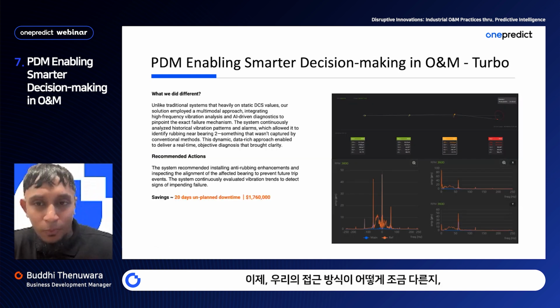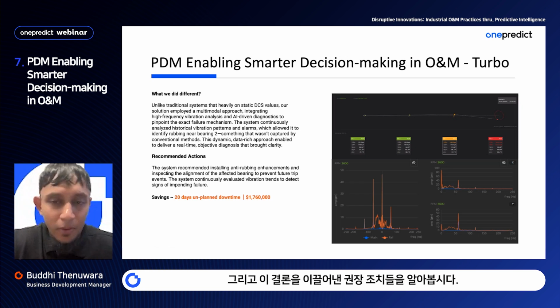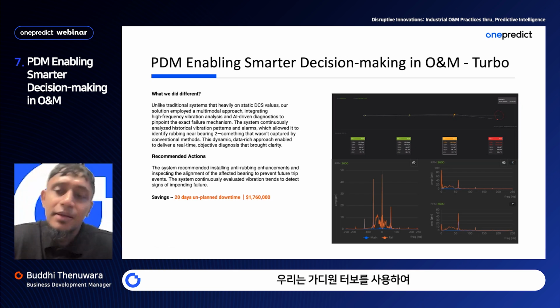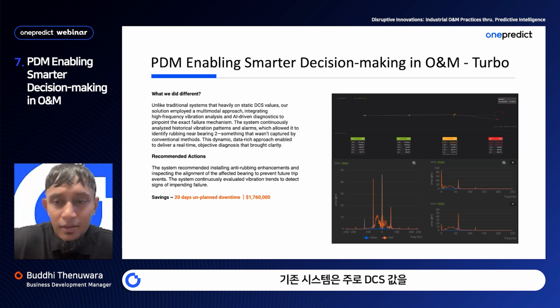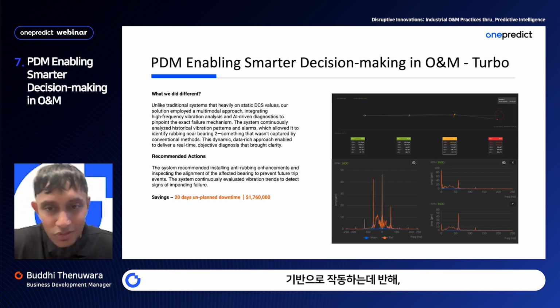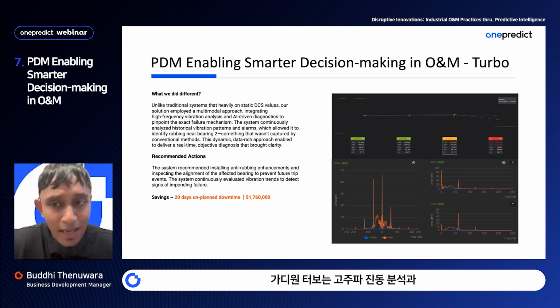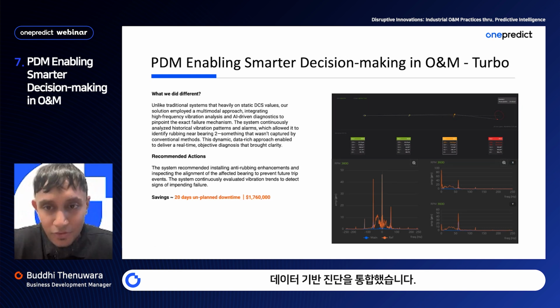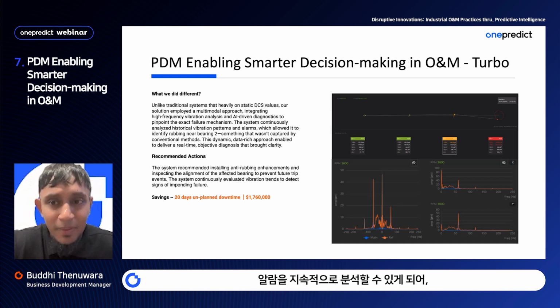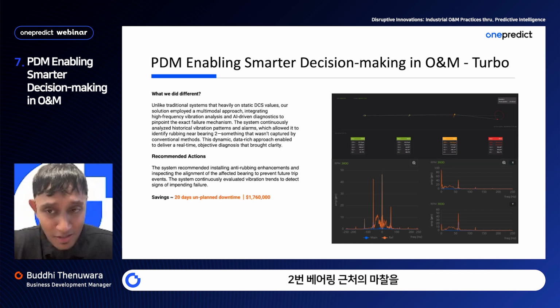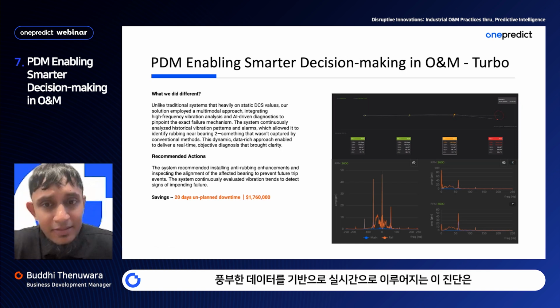Now let's explore what made our approach a little different, and the recommended actions that brought this conclusion. Unlike traditional systems that primarily rely on DCS values, Turbo implements a multimodal approach, integrating high-frequency vibration analysis and data-driven diagnosis. This allowed the system to continually analyze historical vibration patterns and alarms, leading to the identification of rubbing near the second bearing, a factor that had been previously missed by conventional methods.